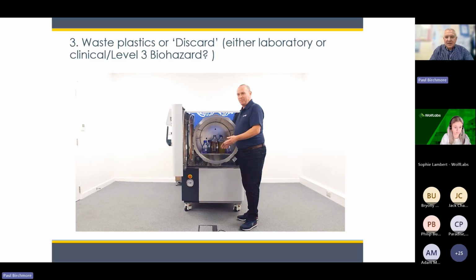Probably just take a slight issue with Neil's video there. I wouldn't recommend putting your hand inside a discard bag. He was only doing that to demonstrate the open aperture of the bag itself. I might even go further and say, don't even constrict the bag at all. Maybe fold it over the top of the discard bin. Perhaps even slash the bag if it's already sealed from transportation between the laboratory and the location where the autoclave is, then even tear the bag or cut the bag with a knife.